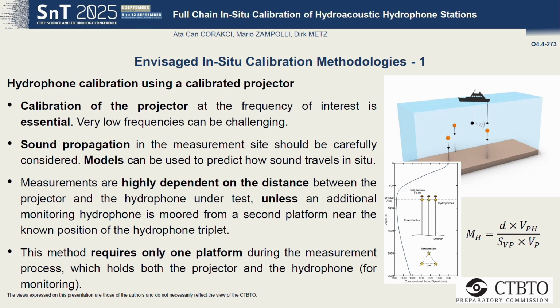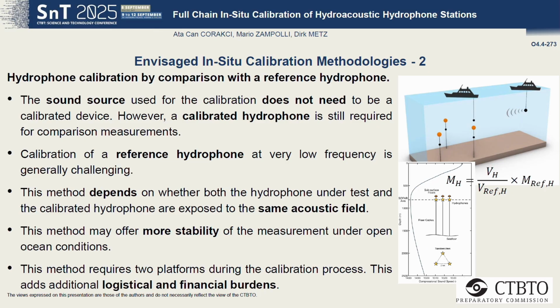But in here, you have to know the distance between the projector and the hydrophone very accurately, because in the formula on the right side, you see D is the distance, and due to the ocean conditions, a change in the distance may affect the result. And the challenge in here is that the frequency range of the PTS is very low, and this is something that we will discuss tomorrow in the metrology session. But the calibration of the projector at those frequencies is very challenging, and there are actually only a couple of NMIs, National Metrology Institutes, that can do this, and this is something that needs to be spread out around the world.